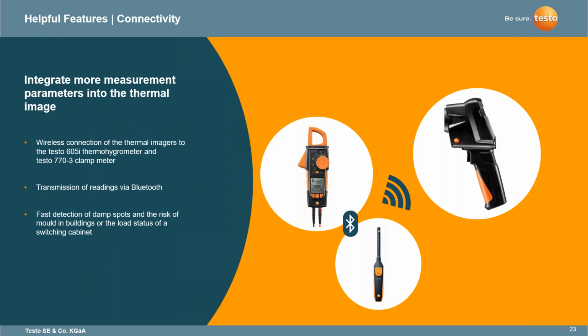Connectivity. We briefly talked about two instruments that Testo sells. We are able to integrate more measurement parameters into the actual thermal image. For example, the 770-3 Bluetooth clamp meter allows you to do electrical components. If you're able to get readings off those components, you can turn on the Bluetooth setting, turn the imager's Bluetooth setting on as well, and have that data feeding to you constantly. So when you are taking images, you're able to get this all in one shot, so that when you're doing your post-processing, you have an amperage reading and your thermal image to show you if there are any hot spots or spots in question or suspect.